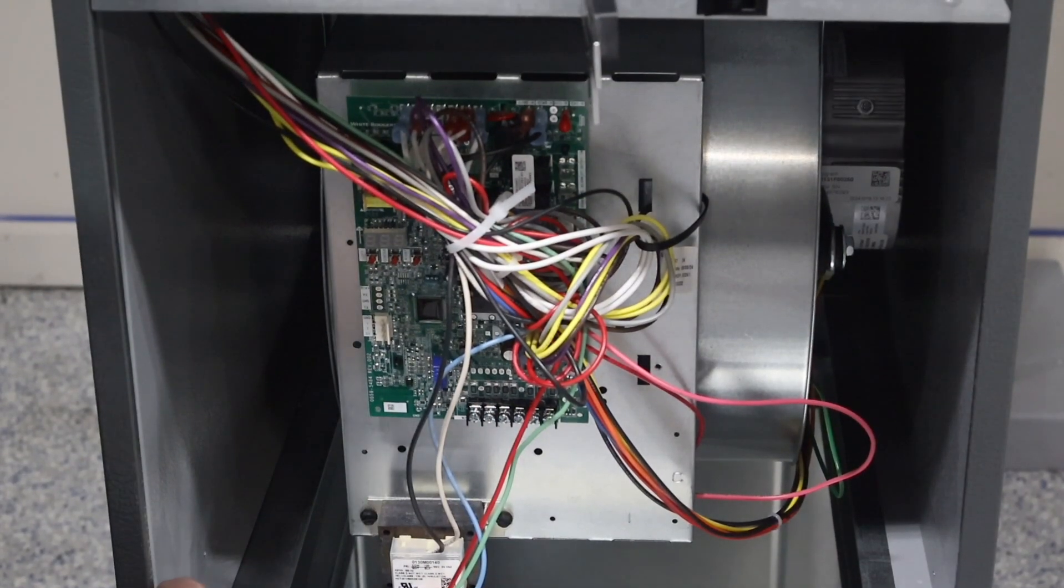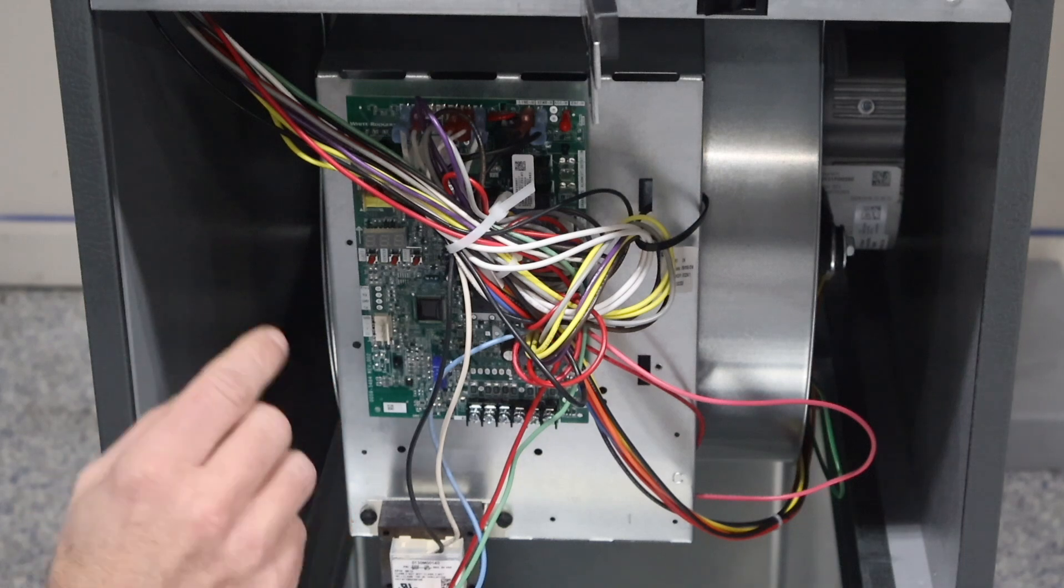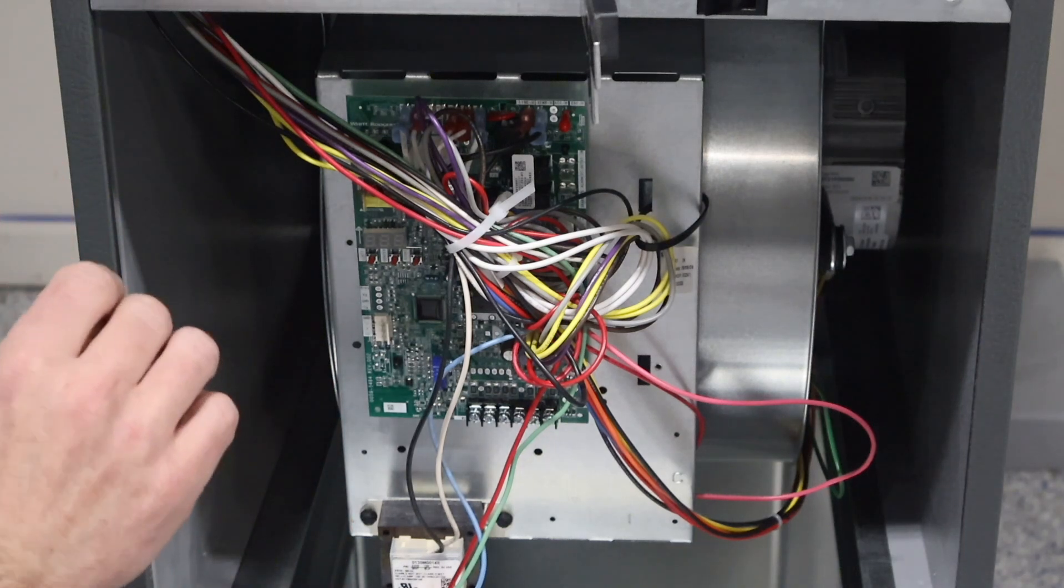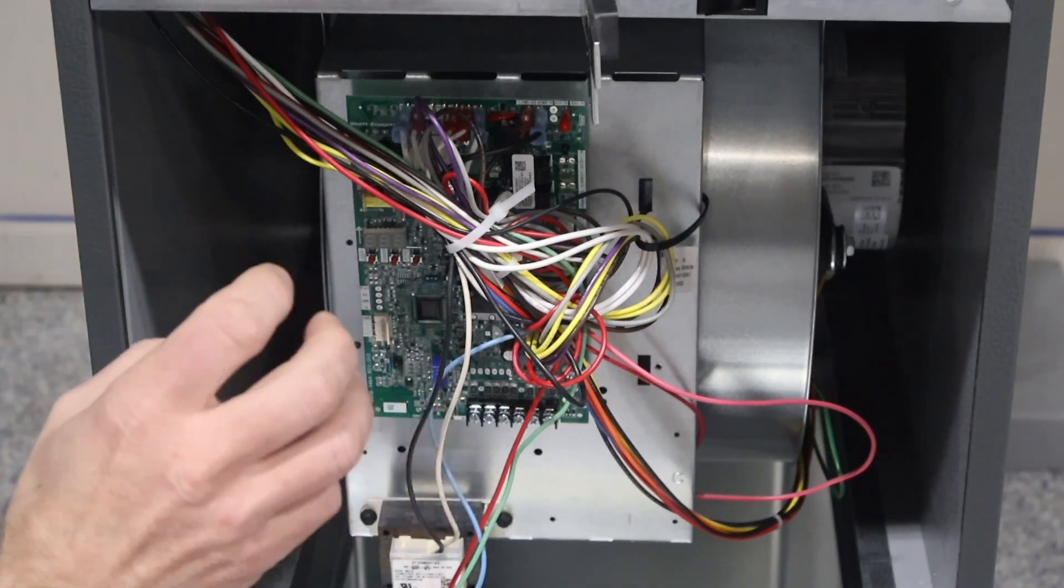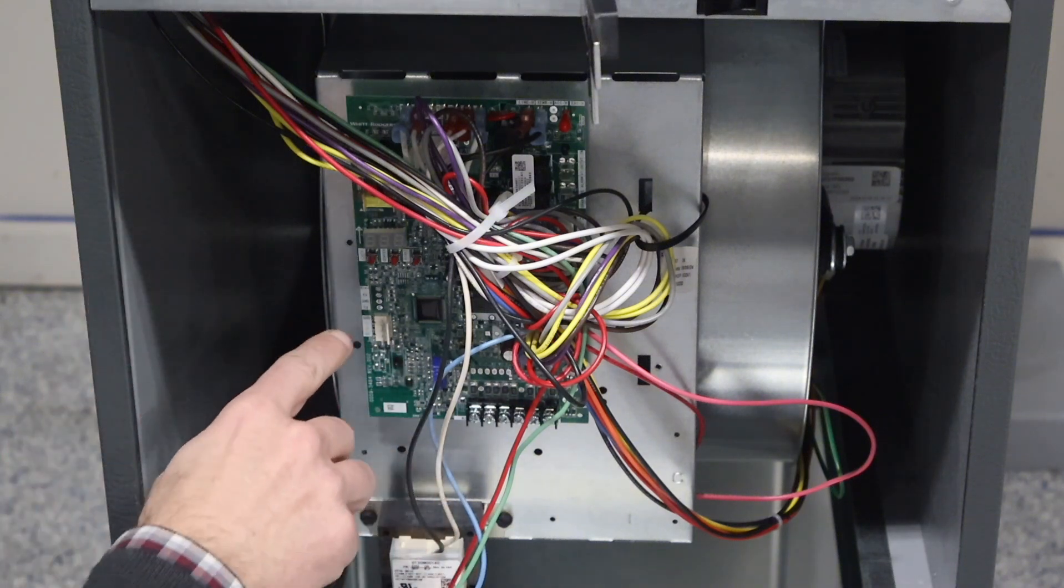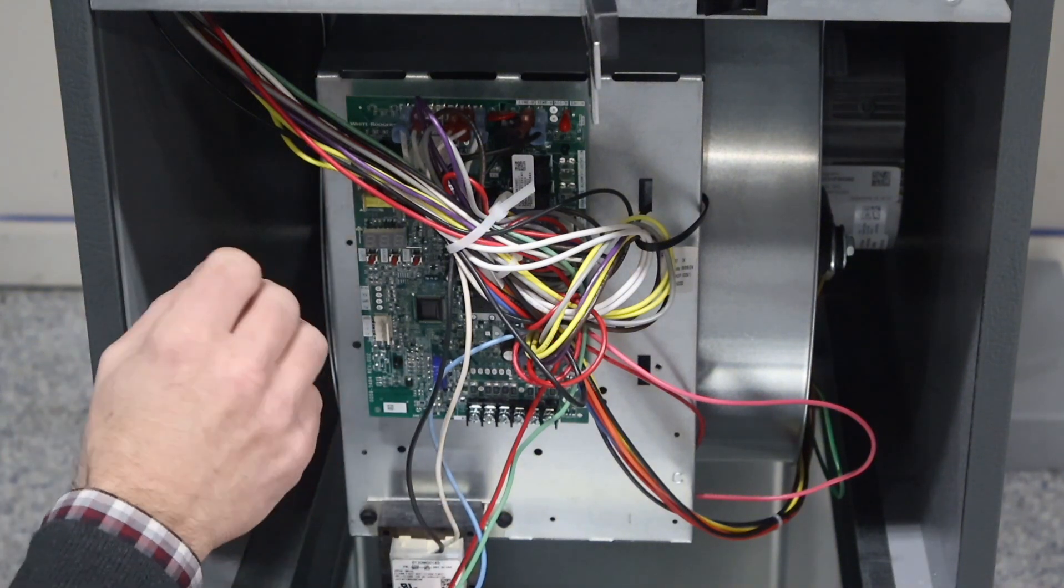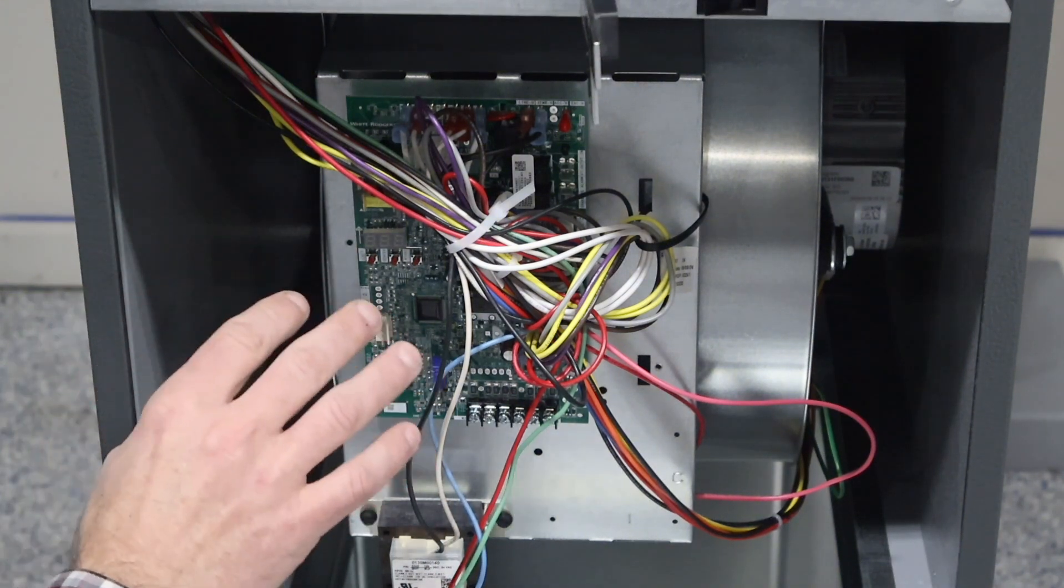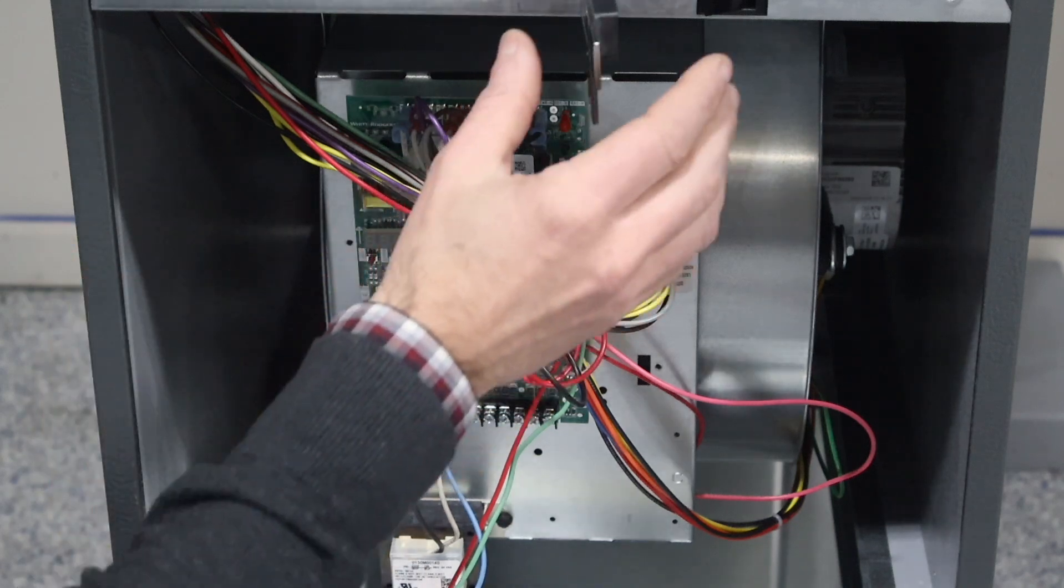Okay, so this furnace comes standard from the factory for an A2L system, but if we're pairing this up against an R410 system, it's going to look for that sensor that we're not going to have. So what we want to do is we want to let the circuit board know to not look for that sensor.